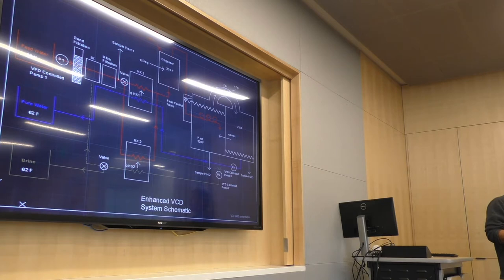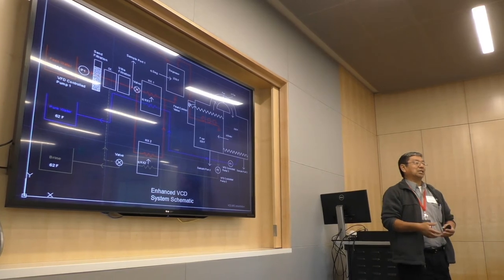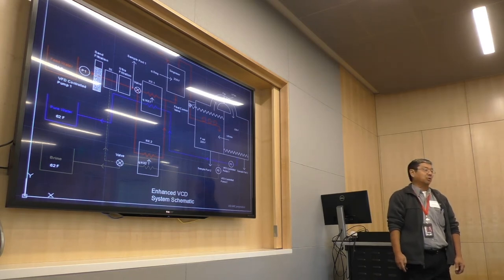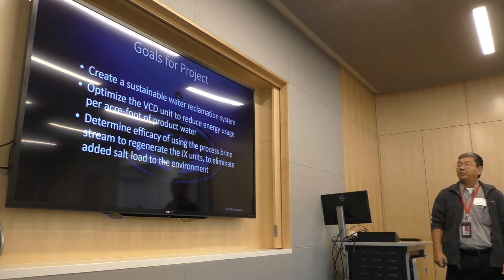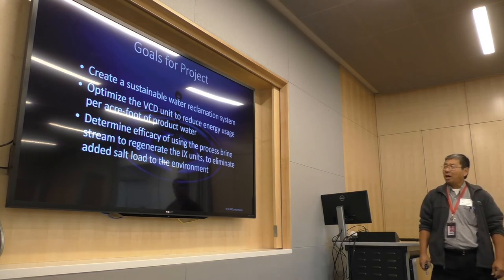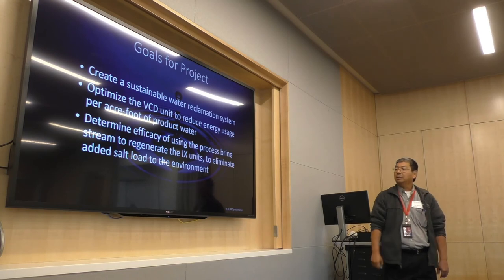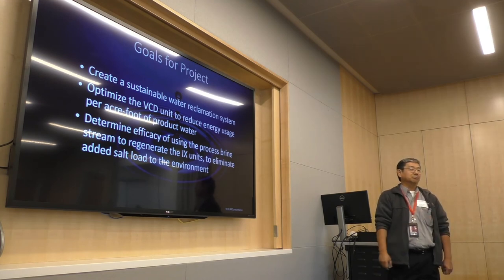As we pull the water out of the drainage system, we have to figure out what to do with the brine — that's the biggest problem. The water itself is no problem. Getting down the energy costs and making a sustainable process is really what we're looking for. We're going into field trials in about a month, starting to move equipment out to the Panoche system. The goals of the project are to create a sustainable water reclamation system optimized for ag use, to optimize the VCD unit to reduce energy cost below the current $2,000 per acre foot, and to evaluate the efficacy of using the process brine stream to regenerate the IX units to make it a truly self-contained, sustainable system.